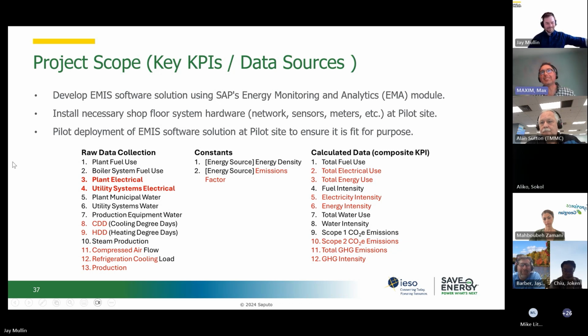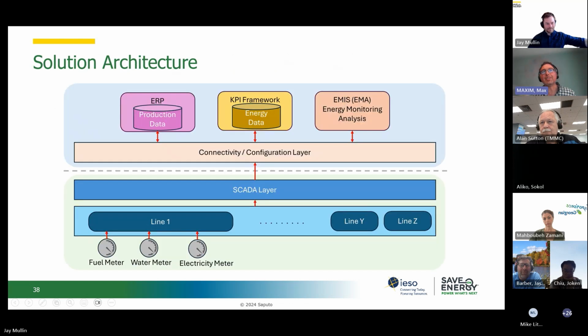This is the platform I was talking about. Below the gray line is everything at the plant level. Every line or piece of equipment would have a fuel meter, a water meter, and an electrical meter. We have multiple of those, and they feed into a manufacturing control layer, or the SCADA layer, which is typically where that aggregation takes place: the meter is sampling every second, but we're actually saving the data point every 15 minutes or every minute, and that's getting done at the SCADA layer.